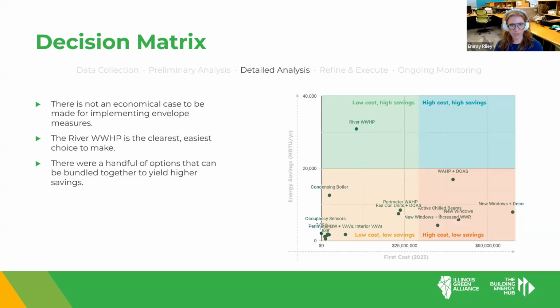Measures in the upper left here save a lot and cost less relative to the other measures. My favorite measure in the project lives in this upper left quadrant: using a reversible water-to-water heat pump not only to reject heat into the Chicago River, which these buildings already do with their condenser water system, but also to extract heat from the river during the heating season. That allows a big shift of heating load from natural gas, which they currently use, to electric, and the heat pumps have higher efficiencies than their natural gas heating. I love this measure because its impact speaks for itself, but it's also a unique asset to the building.